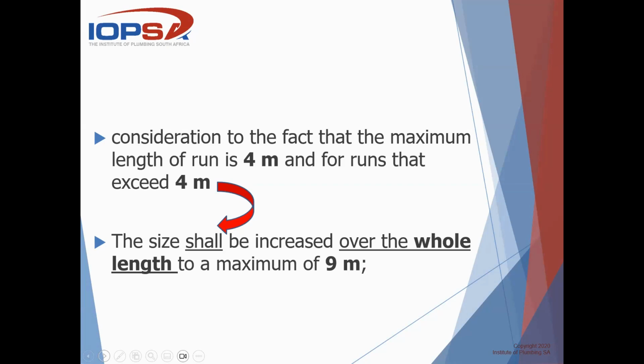That special requirement is that it shall be upsized or increased over the whole length to a maximum of 9 meters. Now, you do see in my presentation that the words whole length are important, and a maximum of 9 meters is where that cutoff point is.